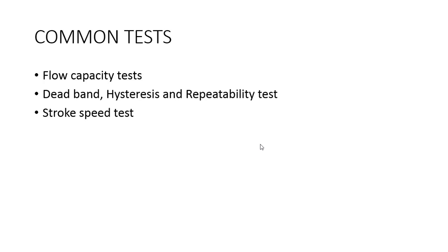Second is dead band, hysteresis and repeatability test. Here there is a standard, ISA S75.13, which gives the guidelines to perform this test. Next is the stroke speed test. It is done to check the valve opening and closing time as per customer requirement.